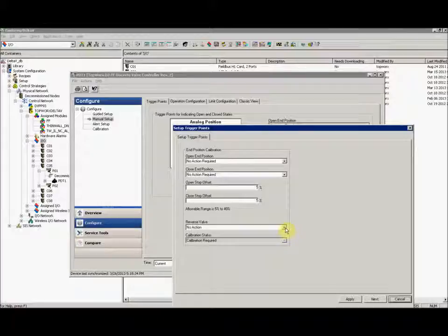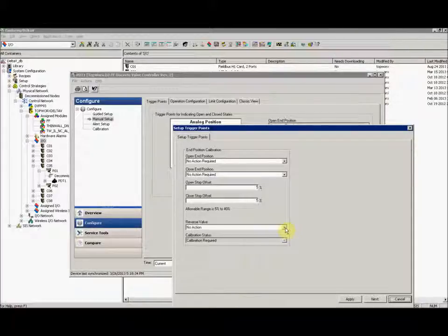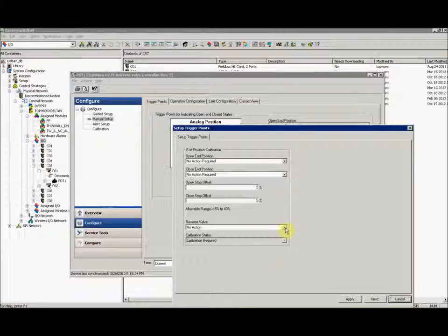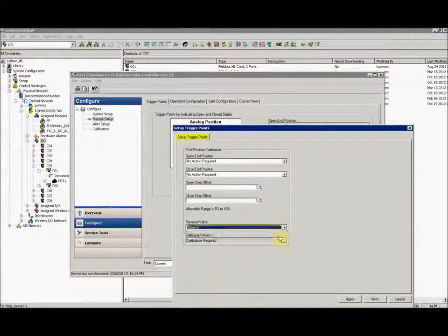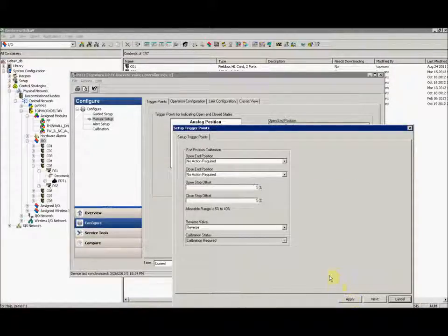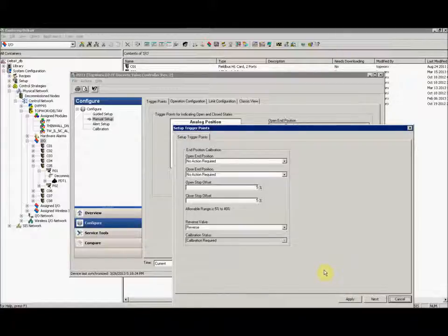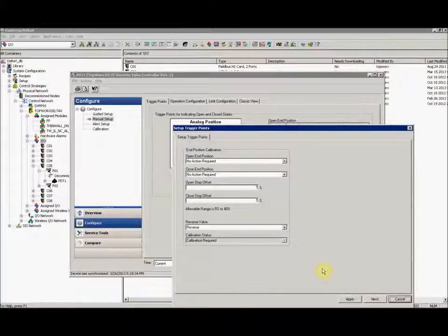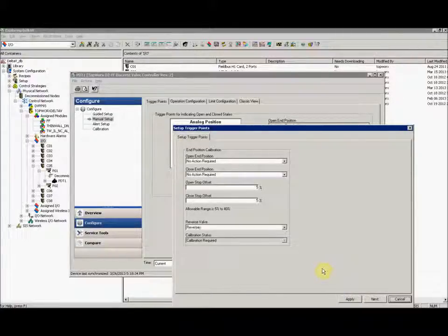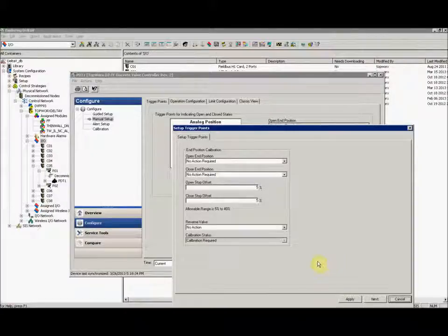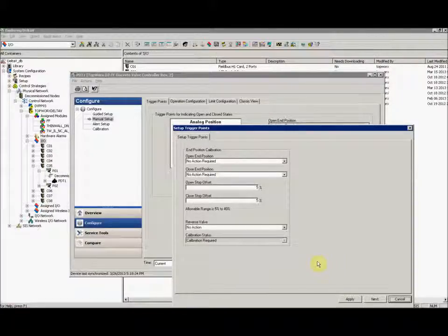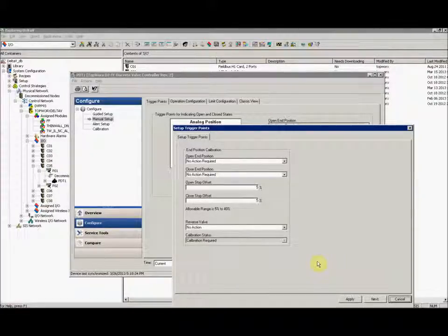Now, towards the bottom, you will see a window labeled reverse valve. Select reverse and hit apply. It should reverse your valve. If it's closed, it will move to open, and if open it will move to close. And this is how you can stroke between open and close via AMS.